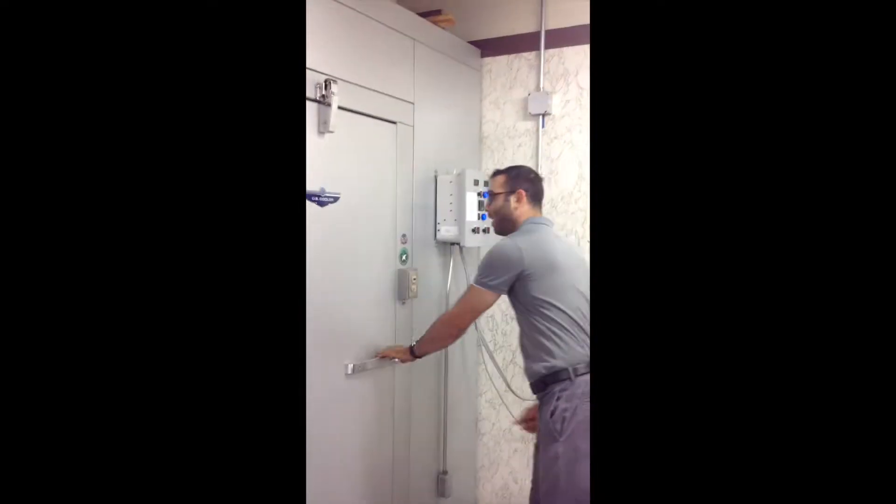Profile running in the heat lab right now, room ambience 40°C. What I'm going to do is take it down and run it over to the wet lab and run an IP66 test. First time we've ever done anything like this on any of our fixtures.